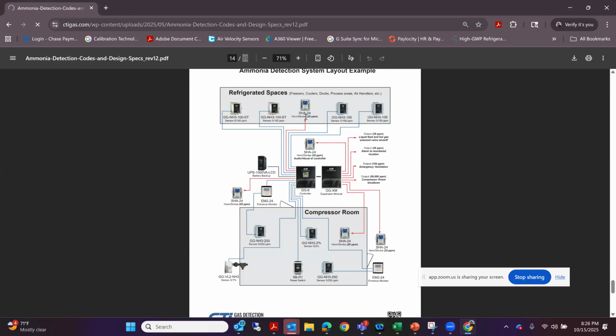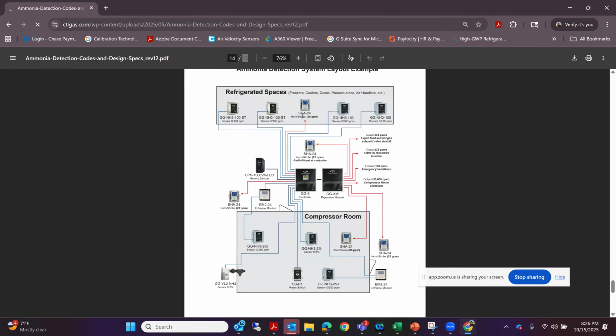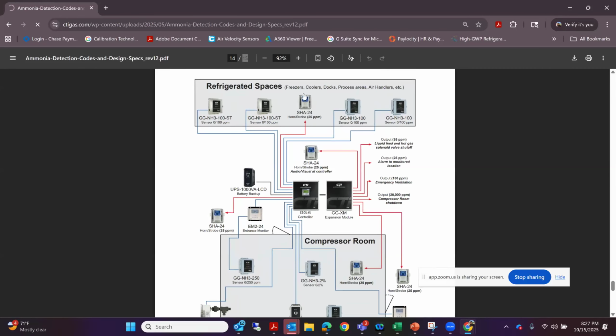But now they're really catching on with these output functions and really keeping an eye on them. We're supposed to be 15 dB above ambient noise in all these areas. If you're out at the freezers and coolers and it's loud out there, with these 100 dB Hornstrobes you might have one every 60 feet or one every 100 feet, and people are realizing that's not quite enough. Luckily, because they are 24 volts and only draw about 150 milliamp, a lot of folks just daisy chain more right off of those Hornstrobes, just to add some more audio visual in the area.